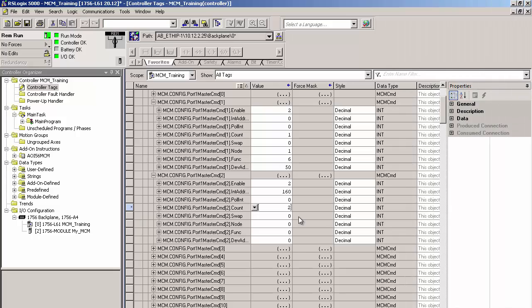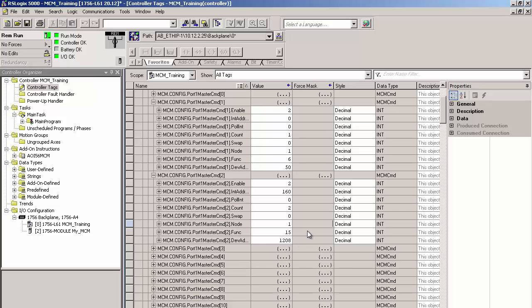This is a write command, so we're going to the write section of our database. The first command is using the first register in write data, so we need to start at address 2, but I'm going to write these bits from the 11th word, which will be write data 10. We multiply that by 16 to get the bit level address, and that gives us 160. For count, we'll enter 2 as the number of registers we want to use, so that's 2 bits, which will encompass bit 160 and 161. Again, we're addressing node 1. A function code of 15 means to write multiple coils. The device address will be 1208. This is the bit level address in the power monitor that we want to write to.